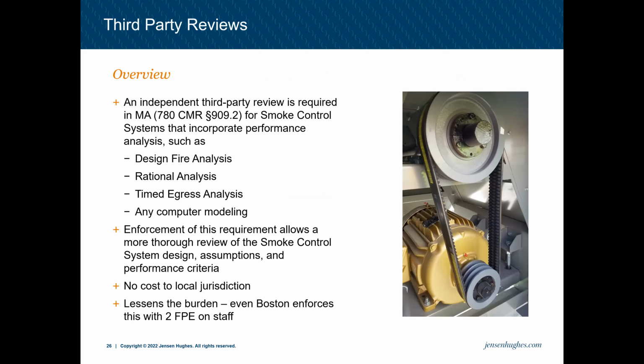Not to go into too much discussion, but smoke control systems do require a third-party review. And that's smoke control systems incorporating a performance analysis. So that tends to be your atriums and your stages that tend to be more the ones that are requiring a third-party review. And it's required by 780 CMR. It's an addition to the building code.